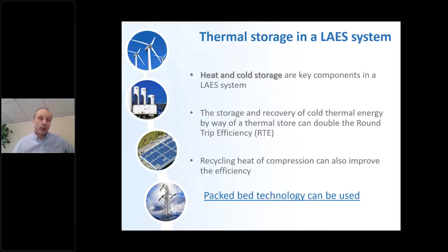Hot fluid and cold fluid are separated by buoyant forces. There's a thermal gradient that's relatively flat and moves up or down depending on whether we're charging or discharging the tank. For example, to store cold energy, the cold fluid enters at the bottom of the tank and leaves at the top. When the fluid stops flowing through the tank, the gradient stays as it was due to natural convection.